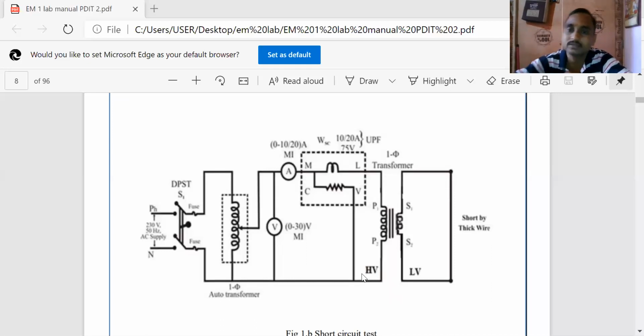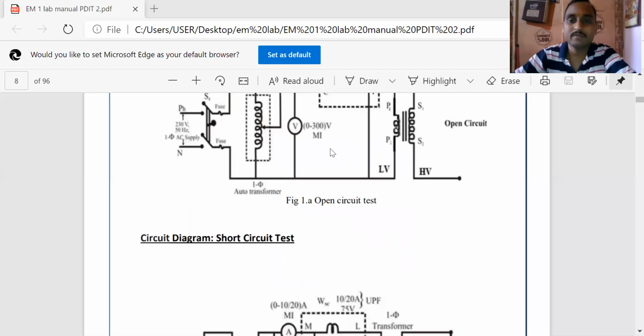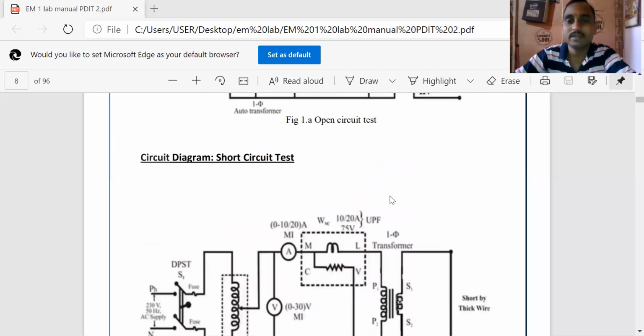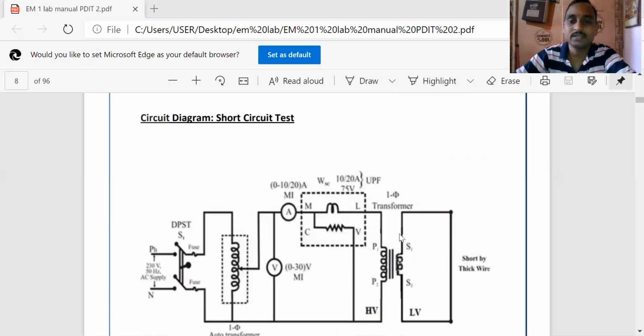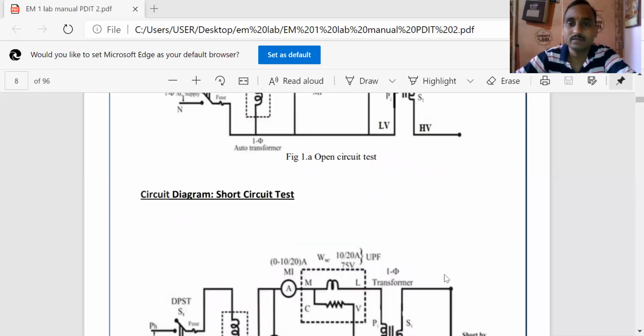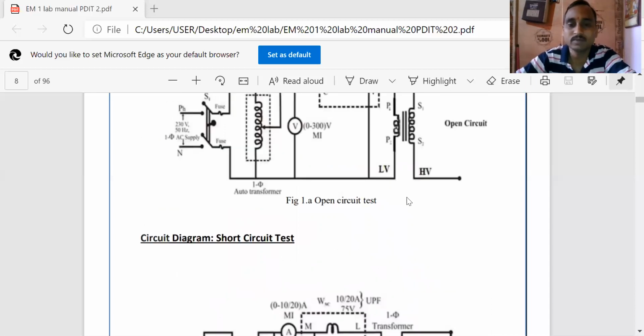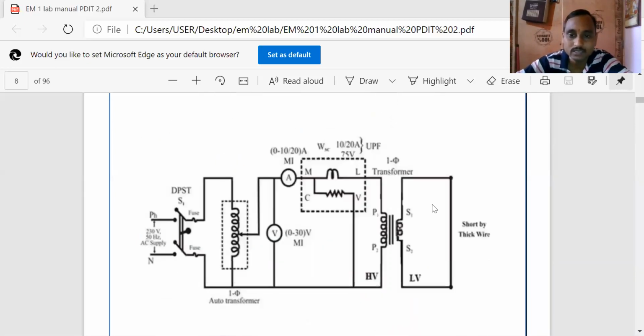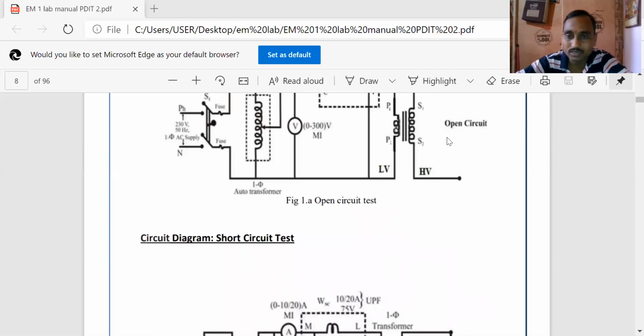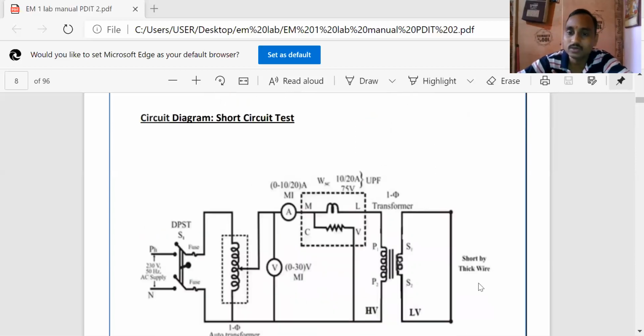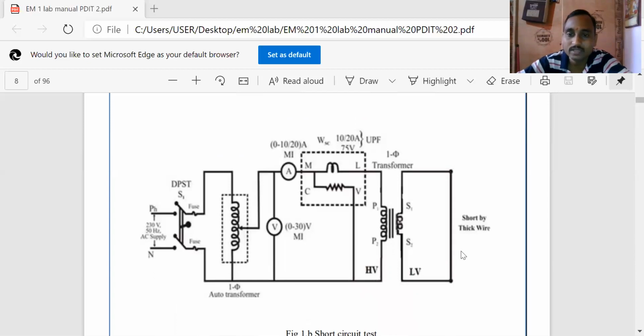For you people, you are going to be confused. That's why we are using primary and secondary. Generally, on the primary we connect all the meters, and on the secondary we perform the open circuit and short circuit tests, irrespective of whether it is the low voltage or high voltage side. For a single phase 1:1 transformer, both the windings are at the same voltage level.